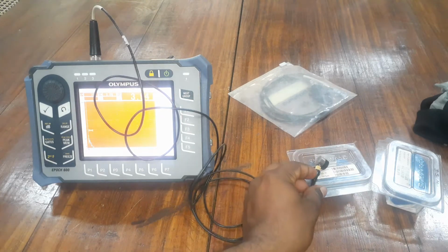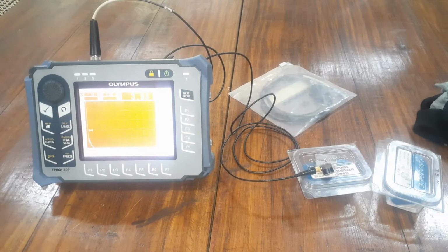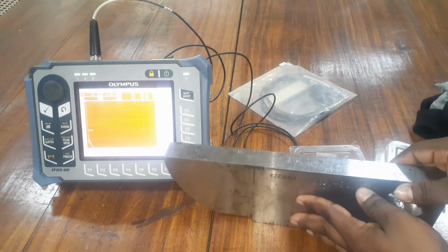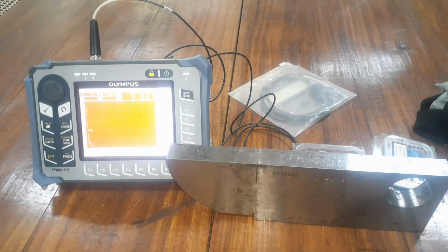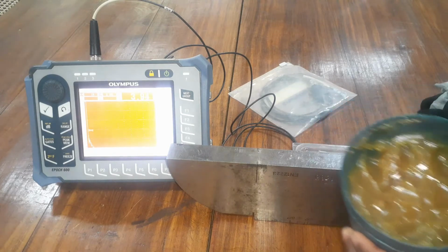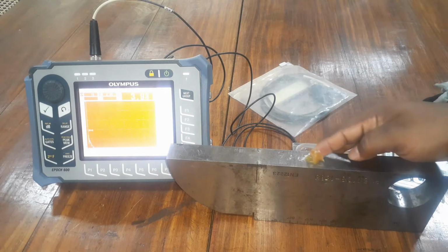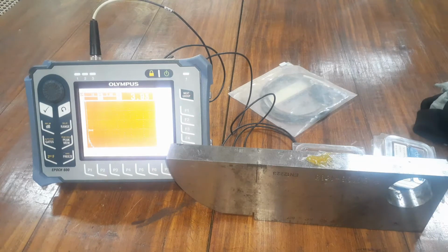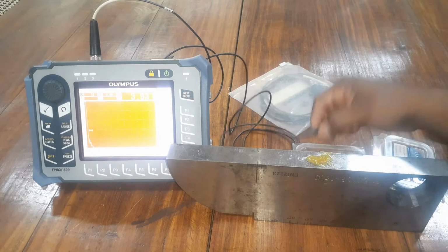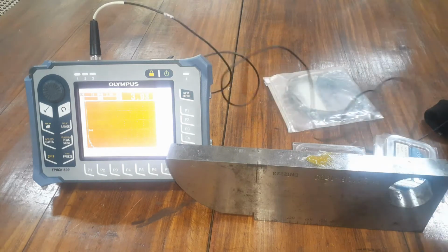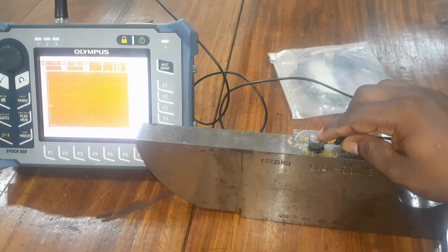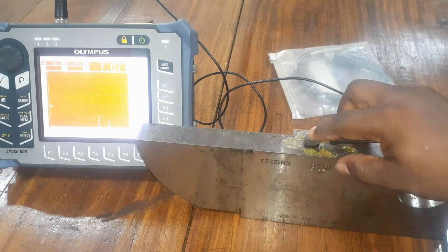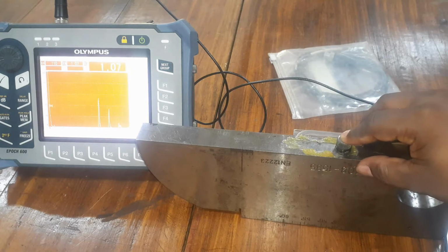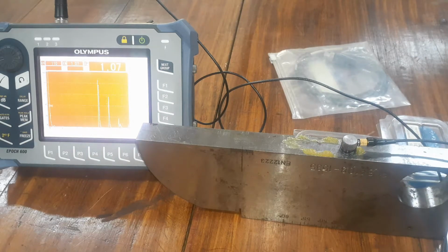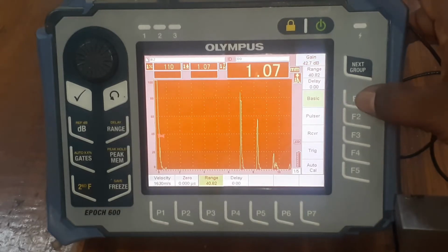First, we are going to calibrate the normal probe. And this is a calibration block. In this calibration, we use grease to remove the air space because ultrasound doesn't travel through air very well. We should find the backwall signal like this. If this is not a steel sample, it is difficult to find the backwall signal without setting the Olympus settings. After finding the backwall signal, you should change the settings.